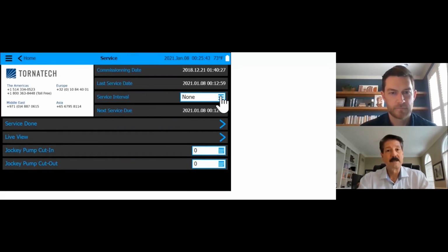Same thing with the interval we could set. Jockey pump adjustments if we want the pressure. Typically, if you don't put the jockey pump cut in, cut out, you're probably looking at about 85% or more accuracy, because it's still going to do it. It's still going to monitor it. But if you put it in there, it increases the accuracy tremendously, probably well over 90% or more.